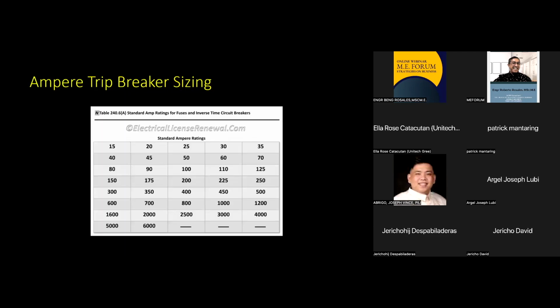Okay, now for the sizing of the breaker, this is a standard table for breakers. The lowest we have in the Philippines is actually 10, not 15. But as much as possible, we avoid using 10 ampere trips. Why? For economic reasons. What if, for expansion, you add another load? It might exceed 10 amperes. Okay?